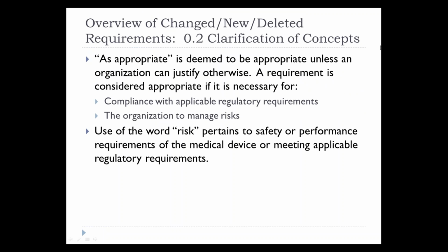Section 0.2, clarification of concepts. You'll see the use of the term as appropriate several times throughout the normative requirements of the standard. As appropriate should be deemed to be appropriate unless an organization can justify otherwise. And a requirement is always considered to be appropriate if it's necessary for you to comply with applicable regulatory requirements or to help you manage risks.